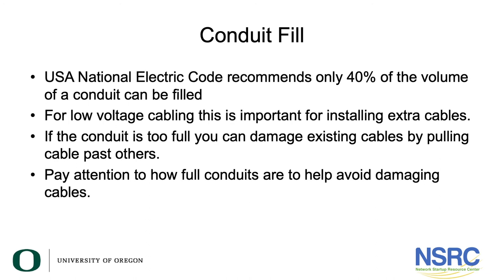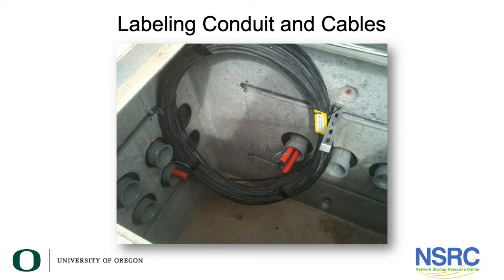Regarding conduit fill: you can't fill a pipe totally full. The U.S. National Electric Code recommends only 40 percent of the pipe's volume be filled. Even if you're not governed by the National Electric Code, that's typically all you want, because it becomes very difficult to pull cable into a pipe with many other cables already in it, and you risk damaging those cables.